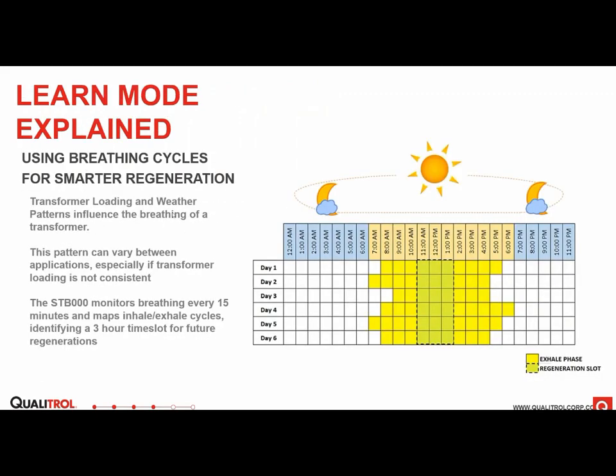So, a little deeper into the learning mode. You can see here this table is a 24-hour window. Transformer breathing cycles aren't always the same. It might shift over time or different seasons, different times of the year. So you can see here, every yellow block is where the breather was tracking a positive pressure on the conservator outlet pipe, so the transformer is exhaling. So it'll know: exhale, exhale, exhale. And it'll pick a 3-hour window when to regenerate. So that's how our learning mode works. It's based on pressure, and it'll pick the best 3-hour window when it knows the transformer is going to be exhaling.